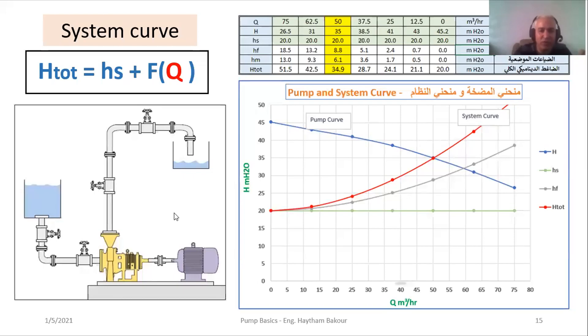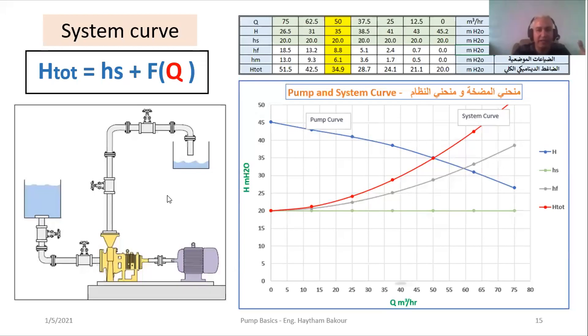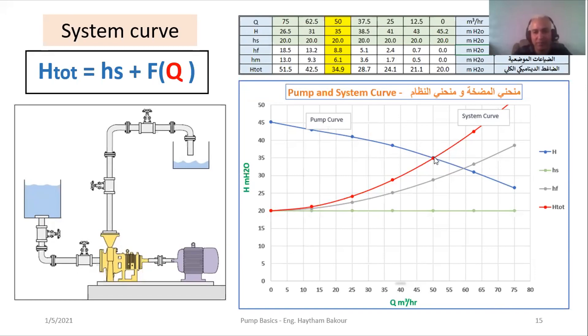We need to calculate until the working point we want, so we can calculate the losses and have the value of the head we need. We need to identify the working point — the flow rate — and have the value of our start point, which is the flow rate and compression. The system curve in red shows the relation between flow rate and the needed head. The blue curve is the pump curve, and that crossing point is the working point we are after.